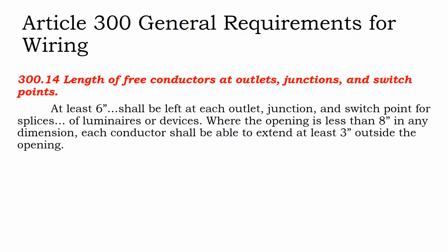So, length of free conductors at outlets, junctions, and switch points. At least 6 inches shall be left inside those boxes so that you can access it and work inside. When the opening is less than 8 inches in any dimension, each conductor shall be able to be extended at least 3 inches outside the opening.